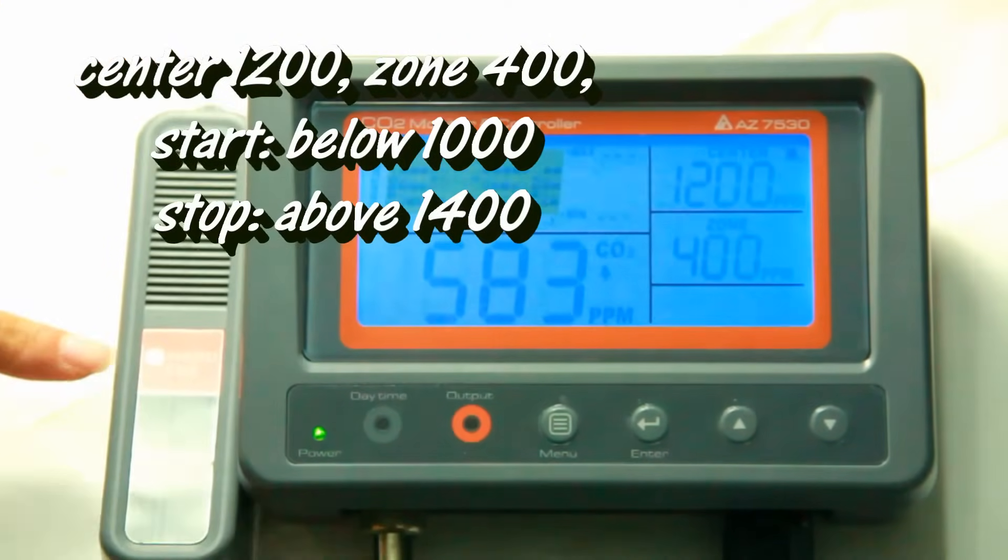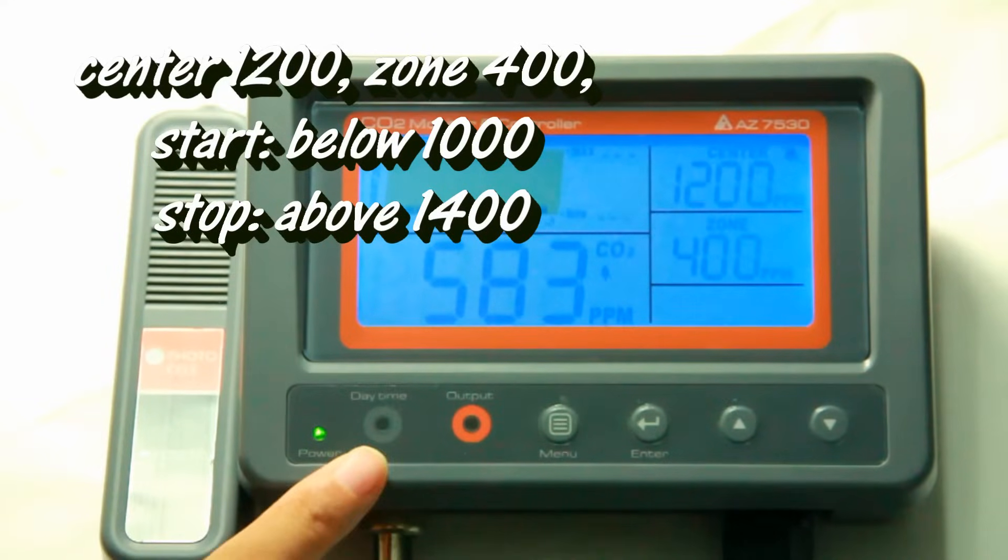Since it is in plant mode, the external device will be powered on while the CO2 is lower than 1,000 ppm and stopped while the CO2 is higher than 1,400 ppm.